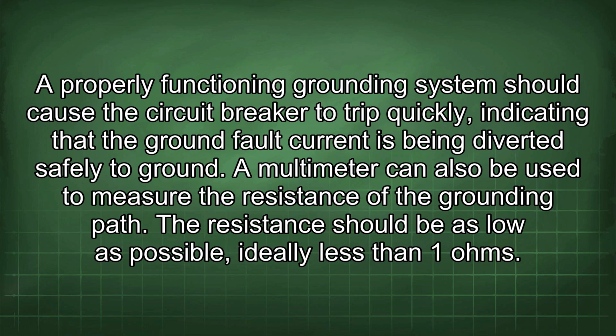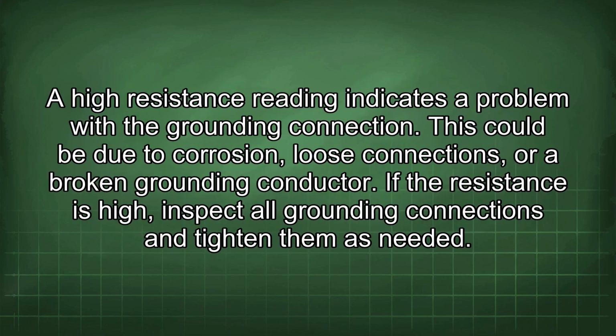A multimeter can also be used to measure the resistance of the grounding path. The resistance should be as low as possible, ideally less than 1 ohm. A high resistance reading indicates a problem with the grounding connection. This could be due to corrosion, loose connections, or a broken grounding conductor.